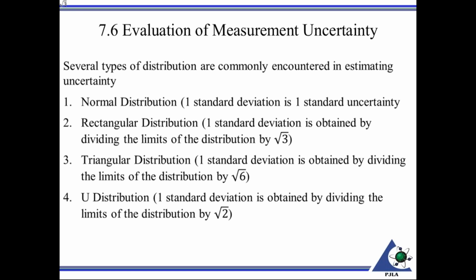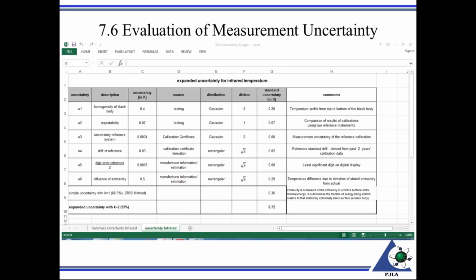So, quantifying uncertainty. There are several types of distributions commonly encountered in estimating uncertainties. We're going to look at four basic ones here. One is the normal distribution, which has one standard deviation. You also have a rectangular. The normal, with the one standard deviation, is divided by 1 to get the standard uncertainty. For a rectangular distribution, one standard deviation is obtained by dividing the limits of the distribution by the square root of 3. We have a triangular, where one standard deviation is divided by the square root of 6. And last but not least, I listed the U or uniform distribution. One standard deviation is obtained by dividing the limits of the distribution by the square root of 2.